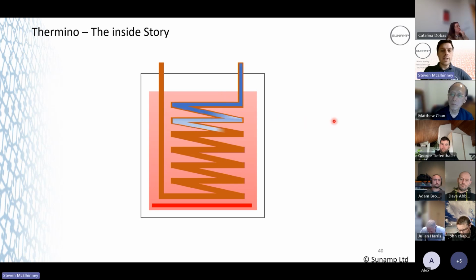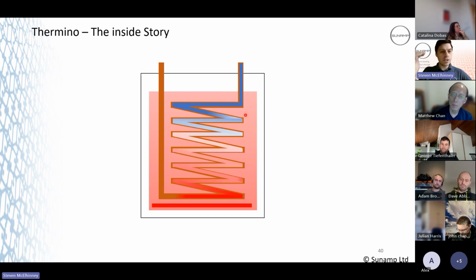But this is a Thermino E. Cold water comes in at the top, exchanging its heat as it goes down to the base of the heat exchanger, and then it comes out hot. So if the customer's used half their capacity, that water's only going to start getting preheated here instead of up at the top. So the ePVs are a little bit different. They discharge bottom to top. So basically they start discharging from the bottom up.